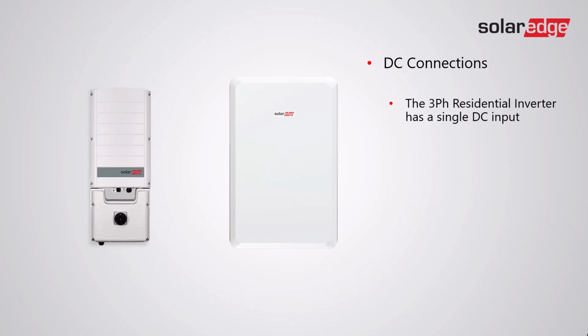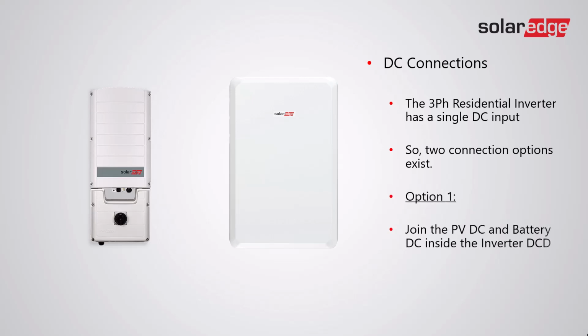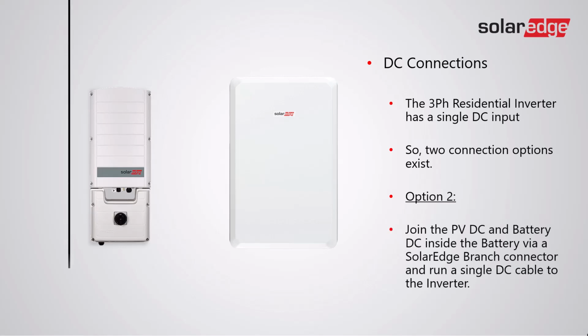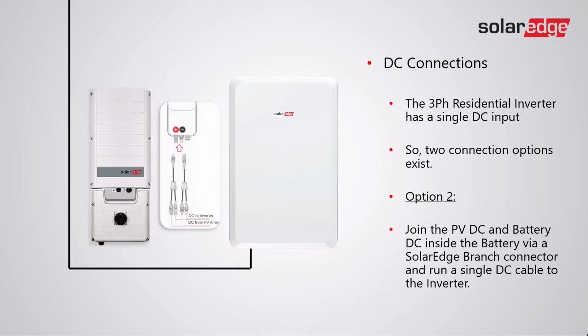The 3-phase residential inverter has a single DC input, so two connection options exist. Option 1: join the PV DC and the battery DC inside the inverter DCD. Option 2: join the PV DC and the battery DC inside the battery via the SolarEdge branch connector, and run a single DC cable to the inverter.